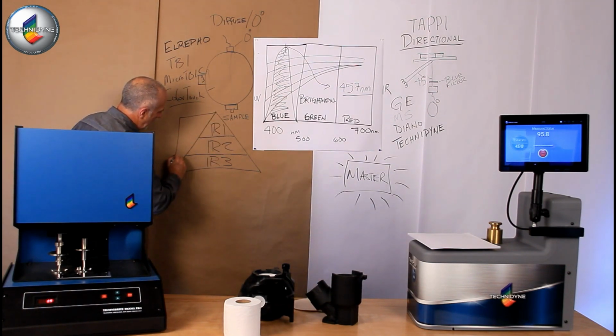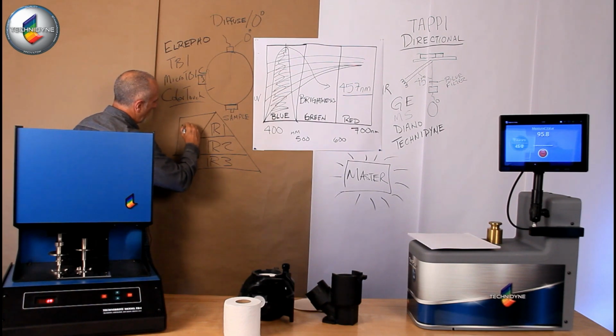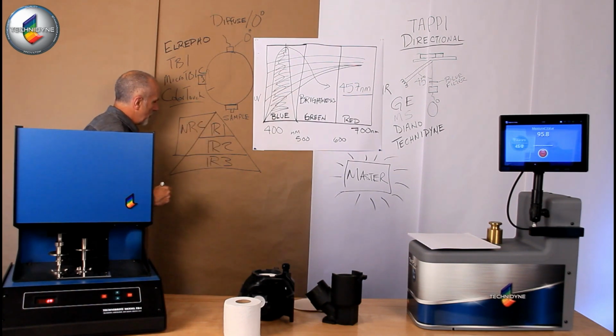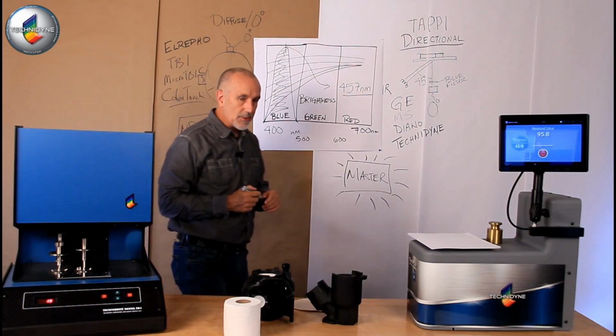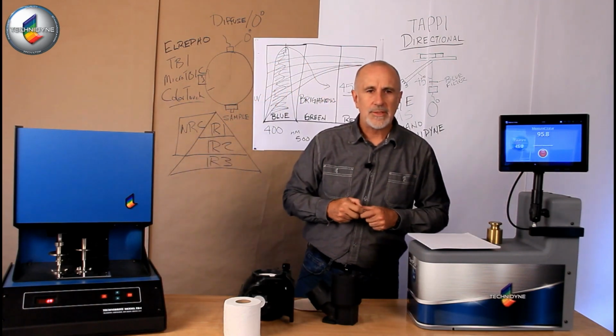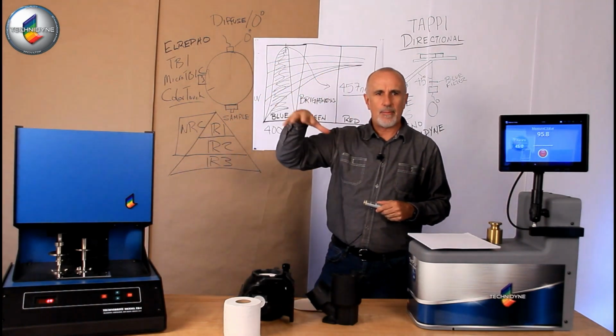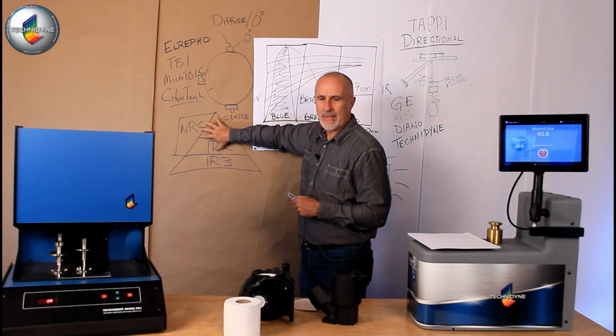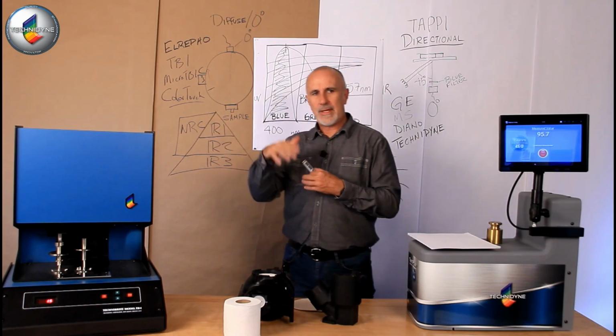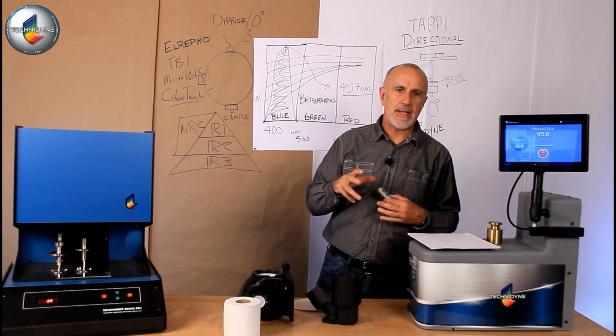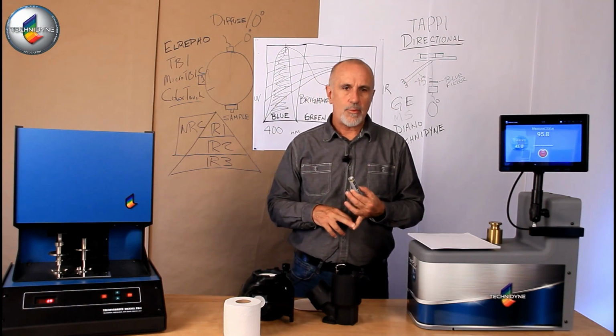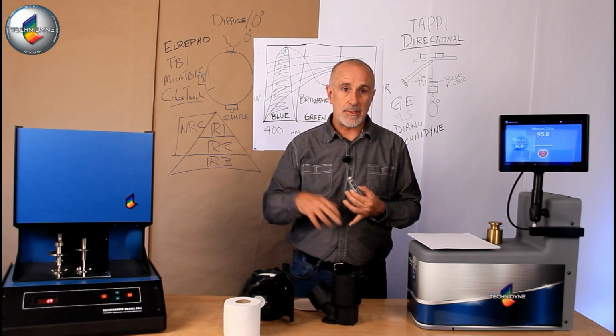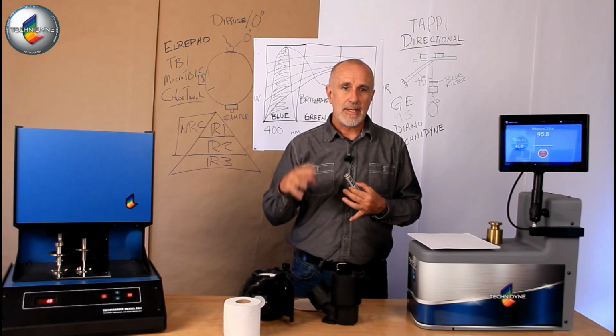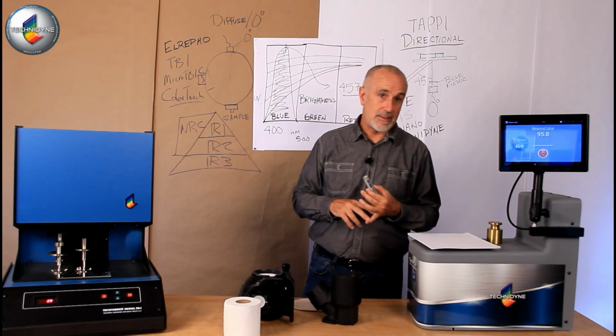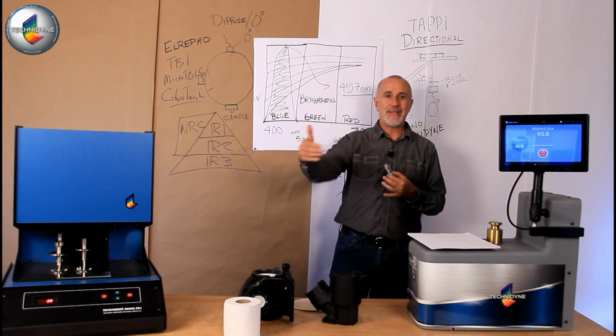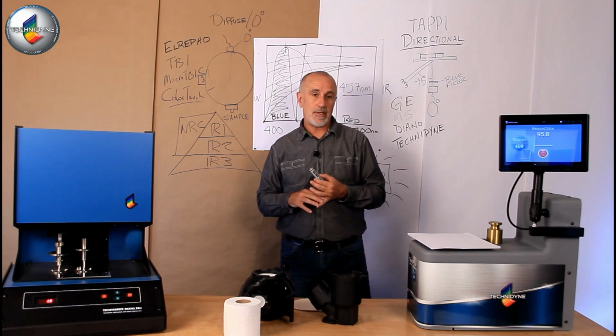We're going to take IR1 and IR2 and give that to NRC, which is National Research Council up in Canada. What the folks there do is maintain the master calibration point. They then, through the ISO standardizing group, work to verify laboratories that they can transfer calibration standards to. And there are currently 4 authorized laboratories in the world for producing ISO optical calibration standards.